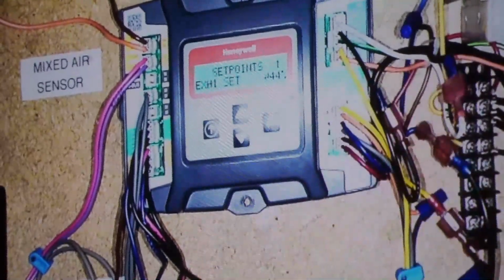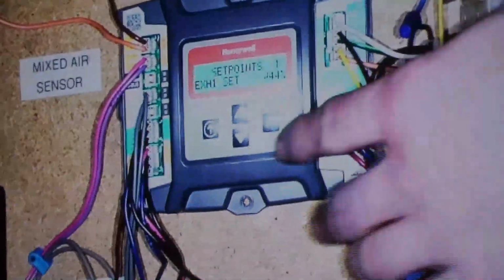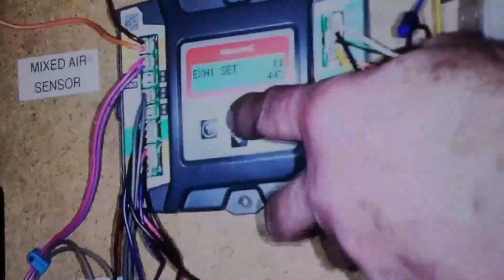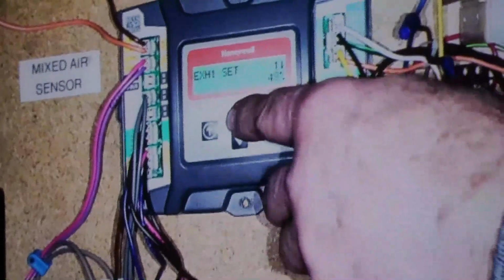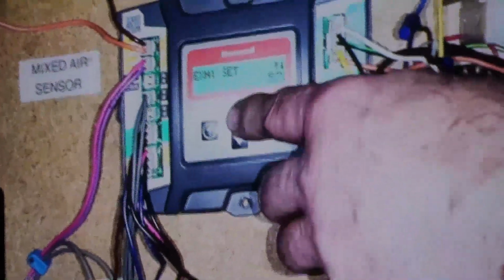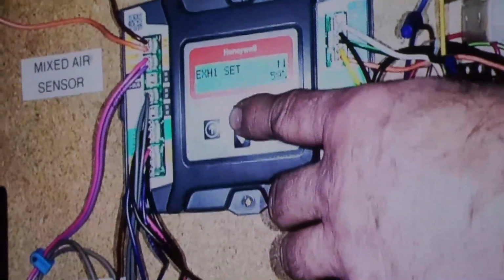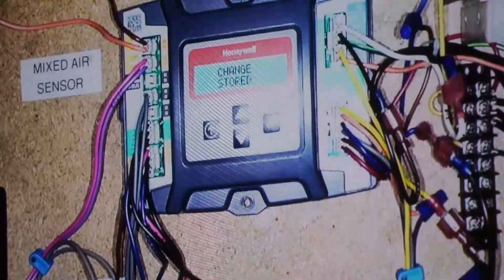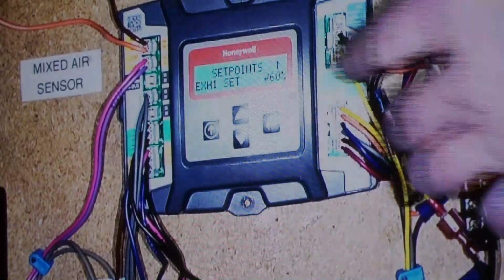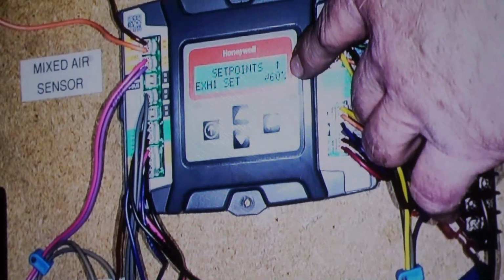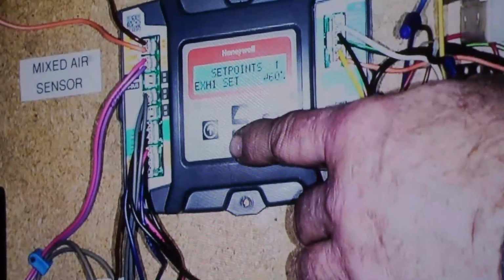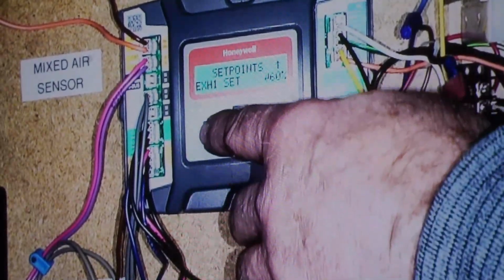Exhaust set point, remember that's how far the damper is open. So anything I want to change, I'm just going to hit enter. Right now it's at 44%, but say I don't have a lot of ductwork on this job, I'm going to say I need it at 60% open before I kick on my power exhaust. So there's my power exhaust, now set to come on at 60% open. And that's the end of that menu.